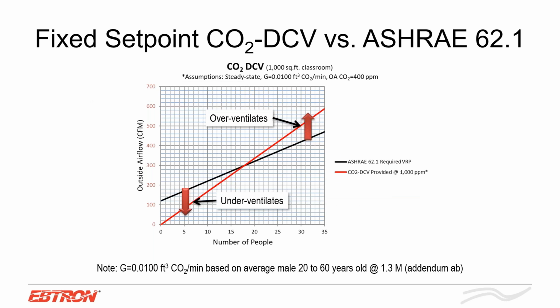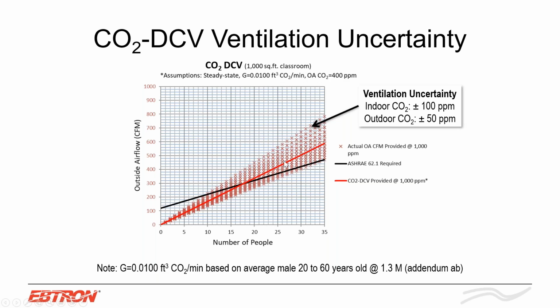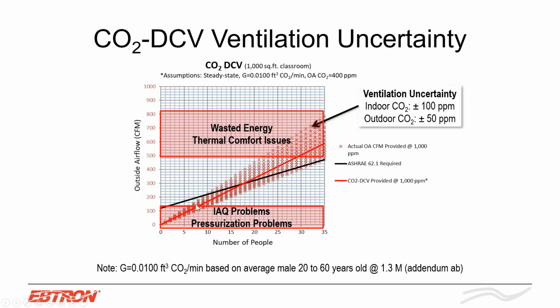Here are some of the issues with this. If you calculate this scenario using ASHRAE 62.1, the ventilation rate procedure, you should be providing this amount of outside air, the black line, based on the population. Well, using this CO2 DCV strategy, you're under-ventilating at low populations, and you're over-ventilating at high populations, thus wasting energy right here. Now let's take a look at a typical CO2 sensor where you have uncertainty, right? Well, you are significantly over-ventilating at the higher populations right here, and you're still obviously under-ventilating at lower populations based on this CO2 error for the sensor. Again, you're going to have wasted energy and thermal comfort issues in your space because you're going to have hot, humid air coming into your space, and you're going to have IAQ problems. You're not going to be complying with codes and standards here at the bottom on the low end at lower populations, right? So how can we help you with airflow measurement?